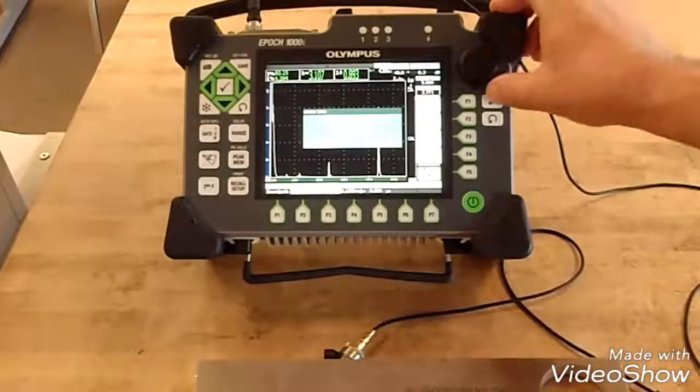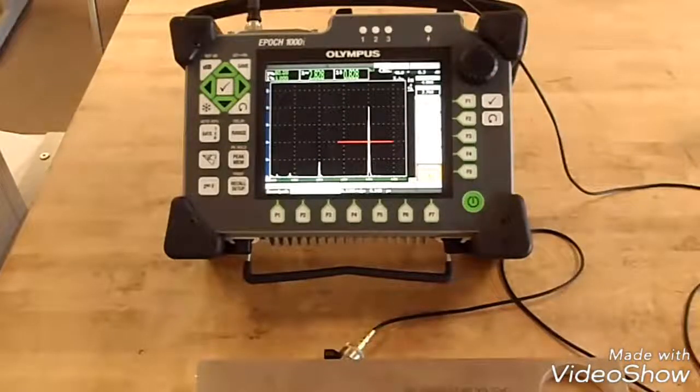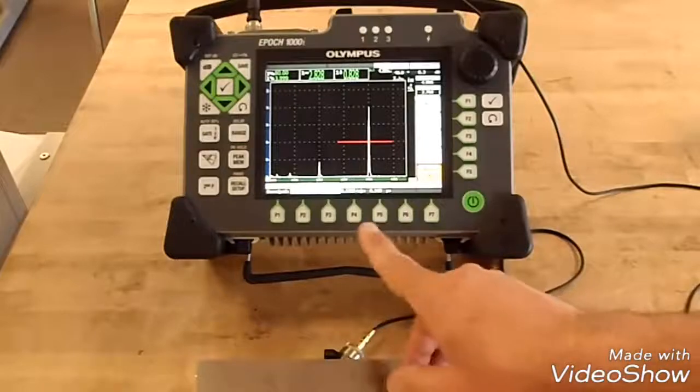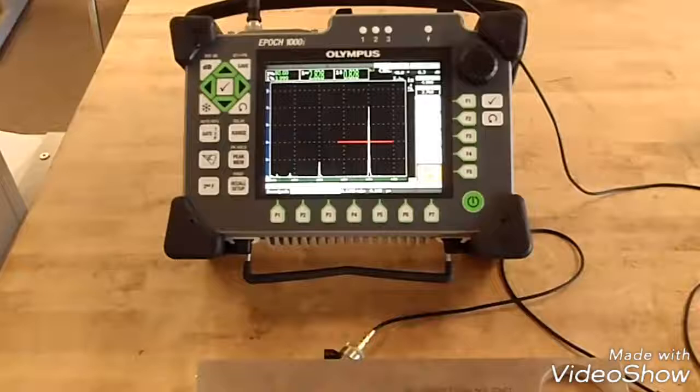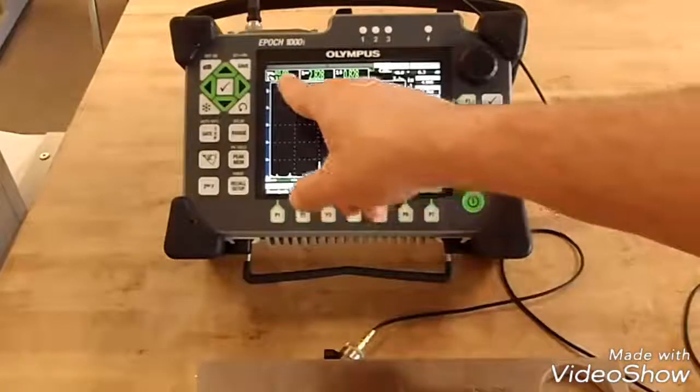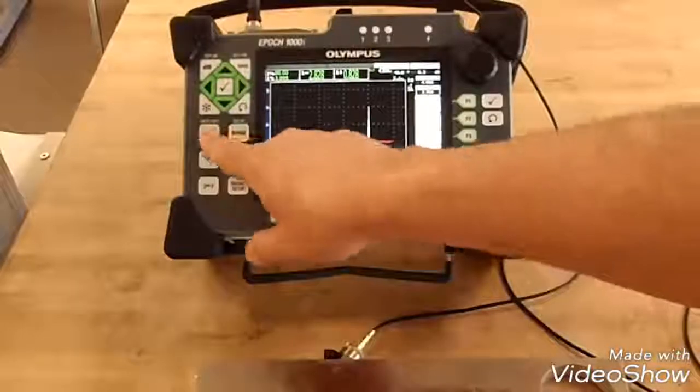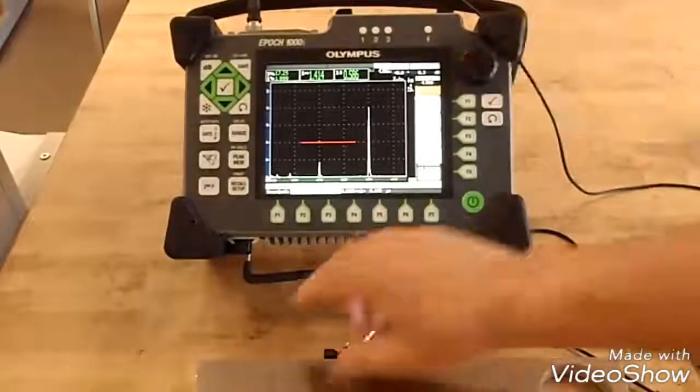There it is. Calculate. Now you've calibrated it. It will automatically change your zero and your velocity to come up with the correct reading. In this case we're reading four inches on the four inch radius and two inch sound path to the two inch radius.